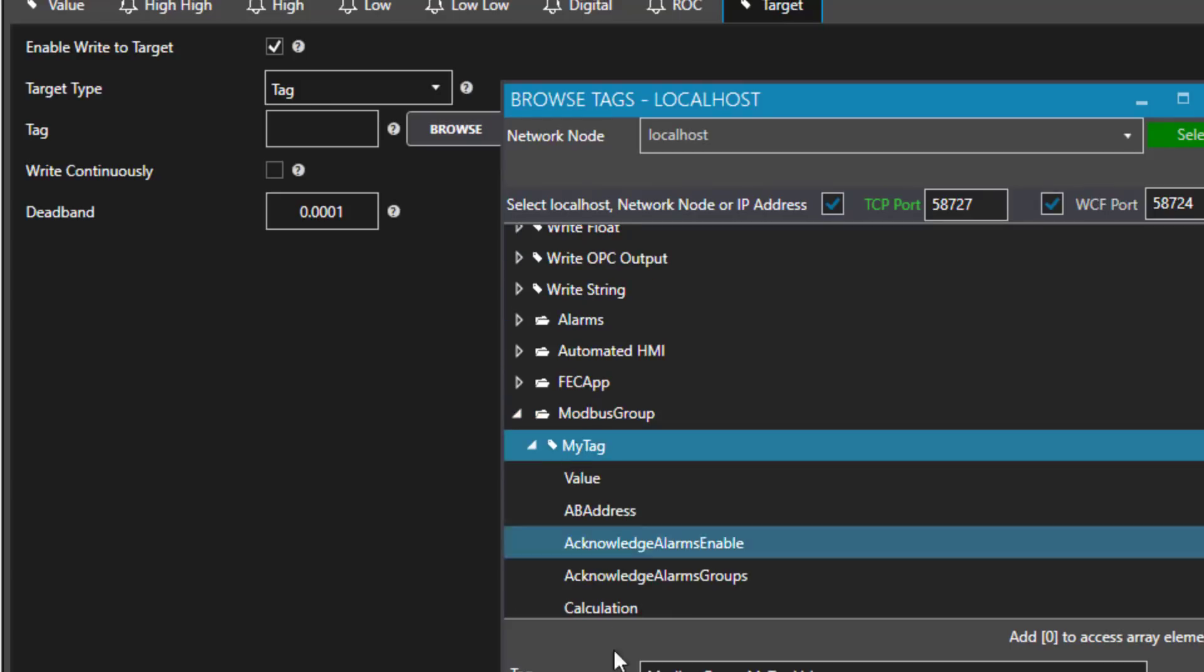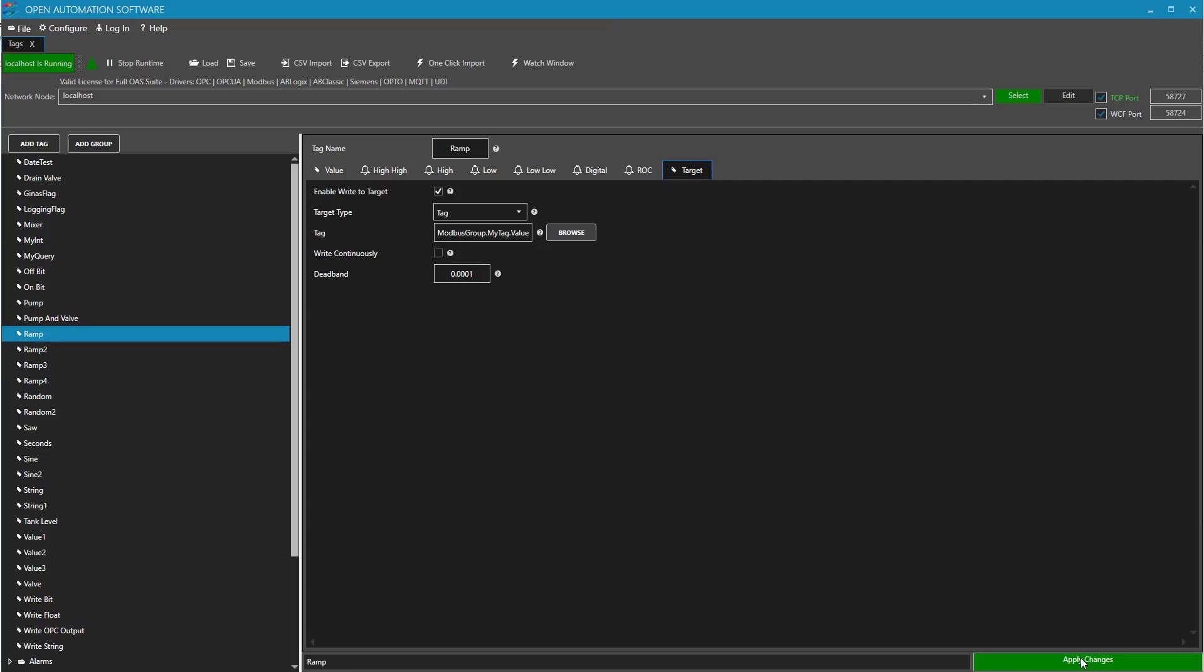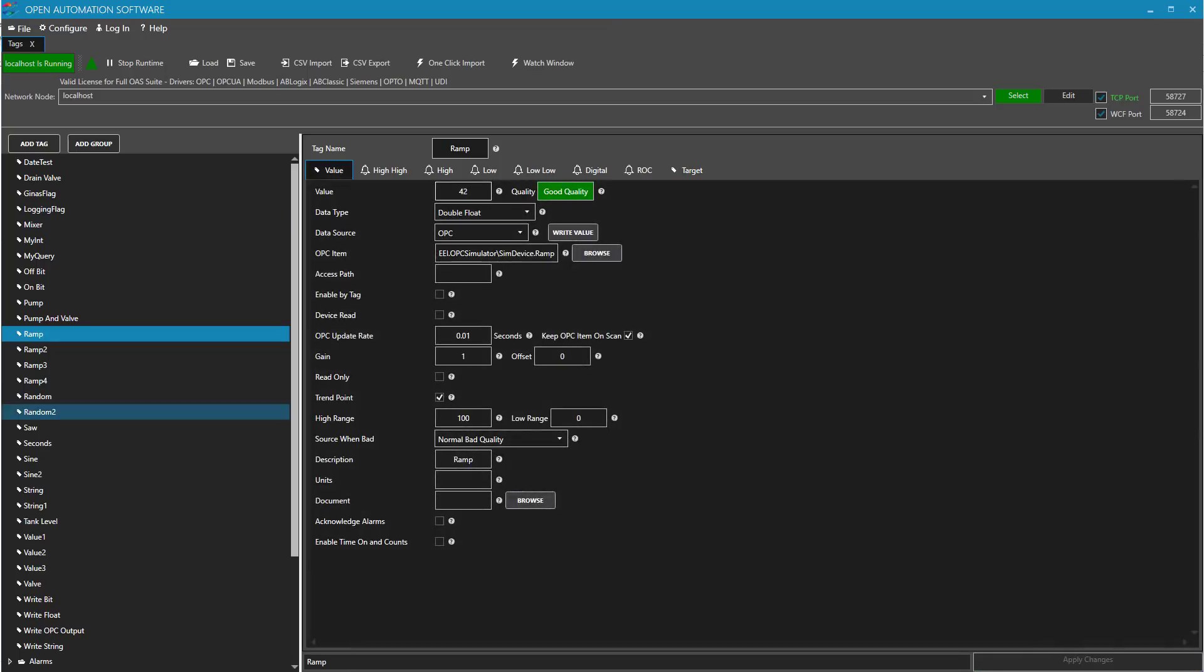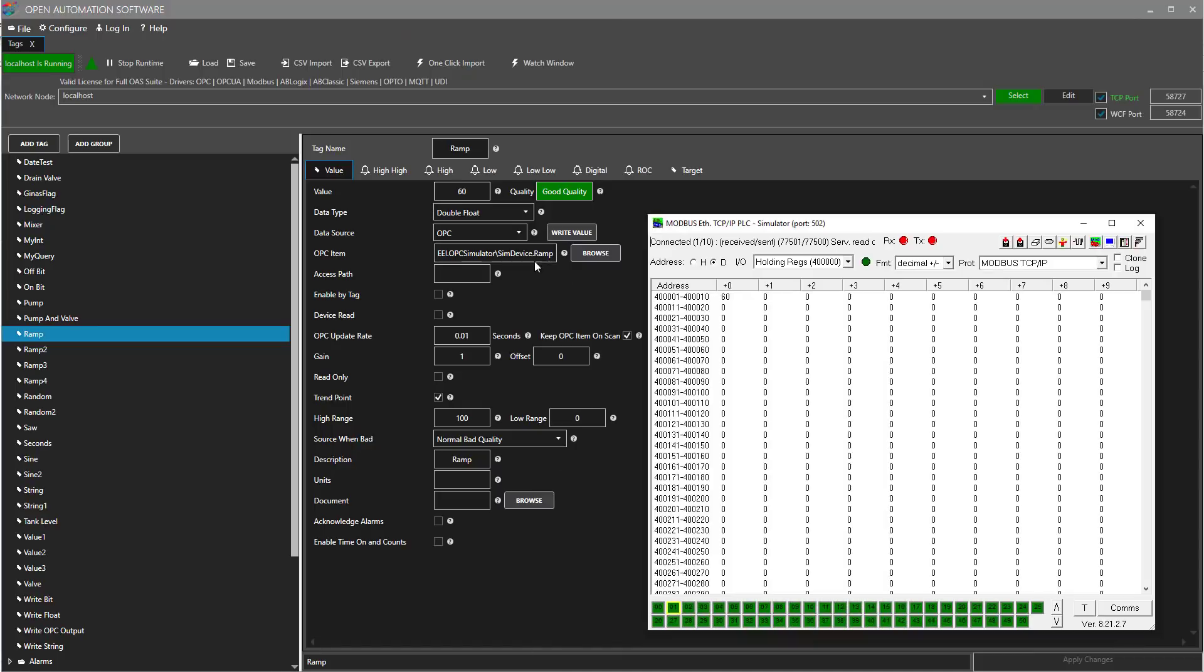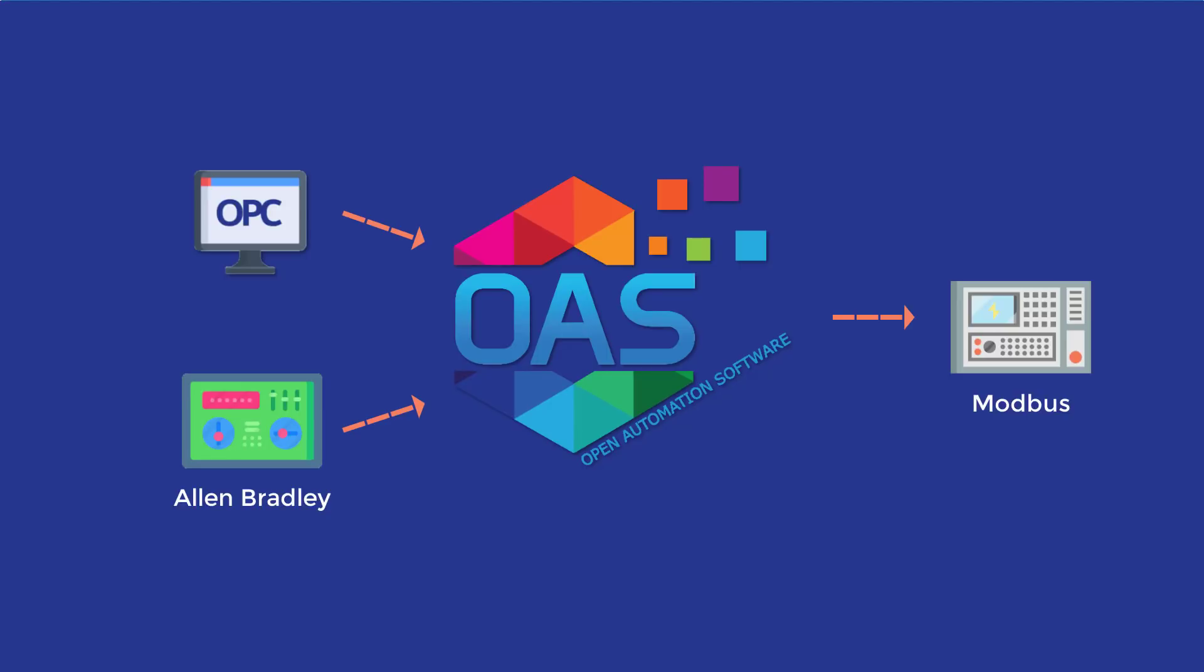When I apply those changes, we can now see in the simulator that we are writing to that holding register, 400001, at a 10 millisecond rate. This is very common functionality to write from one type of controller or protocol, possibly from an OPC server or an Allen Bradley controller, to a Modbus device. Or the other way around, from Modbus to a different set of protocols.